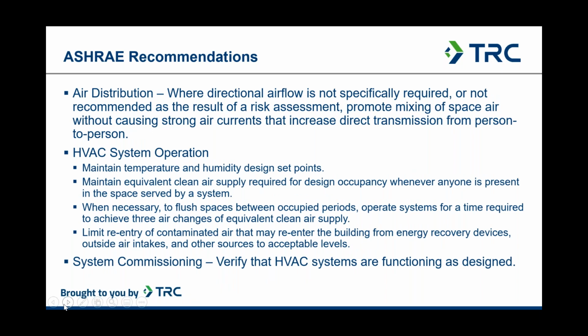Other recommendations of ASHRAE include the implementation of zone or airflow pattern control within a space, extended system operating hours, and also system inspection, validation, and essentially recommissioning. One key point in all of ASHRAE's recommendations is the maintenance of temperature and humidity levels within the space, humidity being particularly important with regard to the virus.